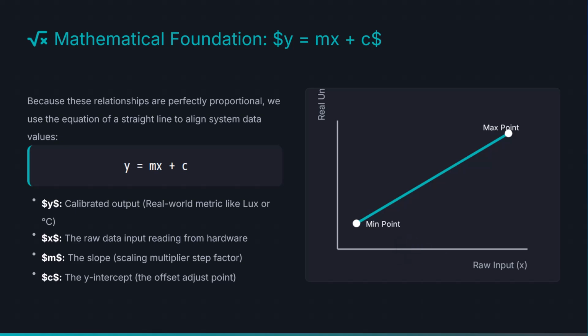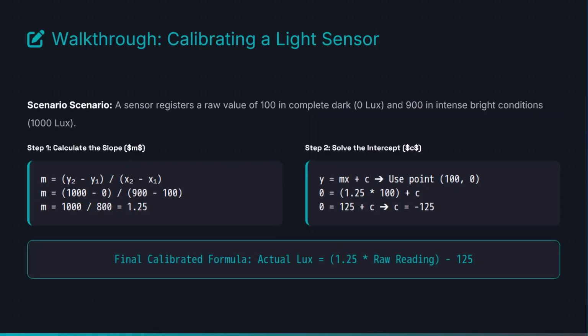The diagram here shows the minimum point up to the maximum point of the raw input. Now let's walk through calibrating a light sensor. Our first scenario is that a sensor registers a raw value of 100 in complete dark, which is zero lux, and 900 in intense bright conditions, which is 1000 lux. Step one is to calculate the slope, which is m.